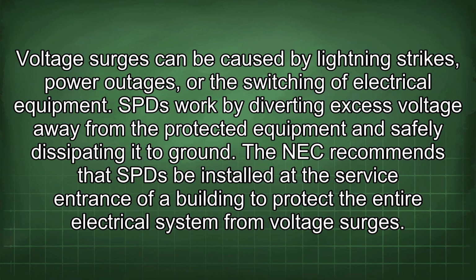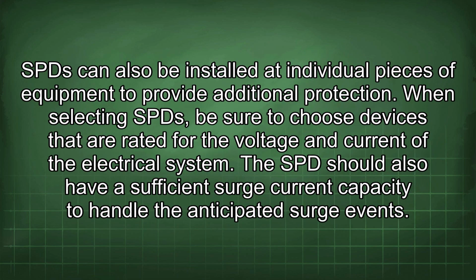The NEC recommends that SPDs be installed at the service entrance of a building to protect the entire electrical system from voltage surges. SPDs can also be installed at individual pieces of equipment to provide additional protection. When selecting SPDs, be sure to choose devices that are rated for the voltage and current of the electrical system. The SPD should also have a sufficient surge current capacity to handle the anticipated surge events.